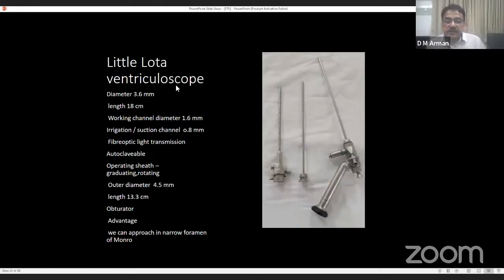This is the Little Lota ventriculoscope used in pediatric patients. It has a smaller outer diameter of 3.6 millimeter, length is 18 centimeter, working channel diameter 1.6 millimeter, irrigation suction channel 0.8 millimeter. It has fiber optic light transmission. It is sterilized by autoclave. This is the operating sheath or obturator sheath. Its diameter is 4.5 millimeter, length is 13.3 centimeter. This is the obturator. The advantage of the Little Lota ventriculoscope is its narrow diameter. We can approach a narrow foramen of Monro in adult and also pediatric patients.